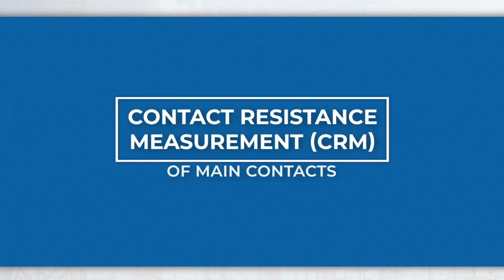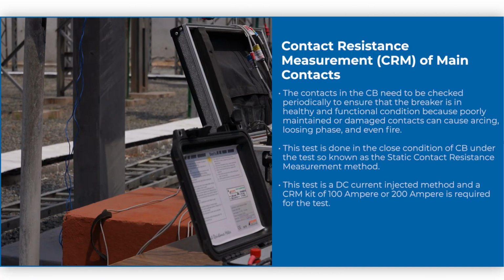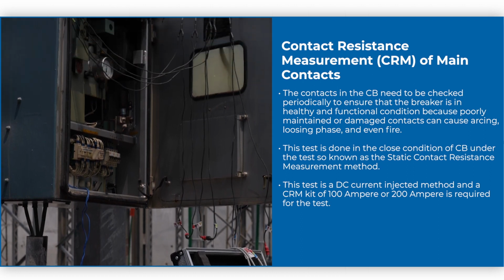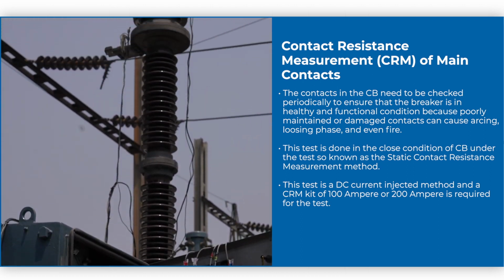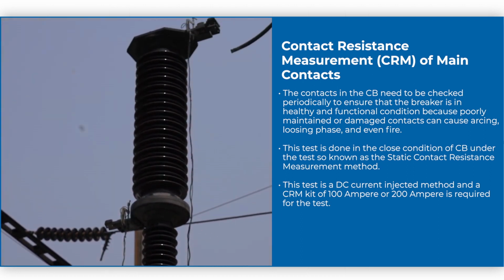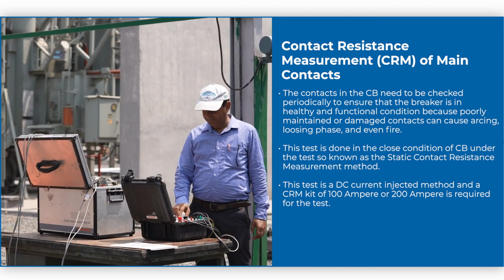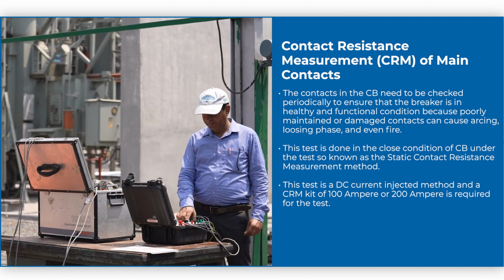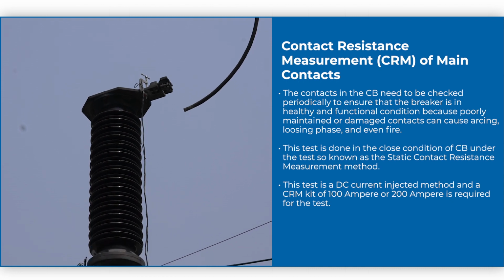Contact resistance measurement (CRM) of main contacts. The contacts in the CB need to be checked periodically to ensure that the breaker is in healthy and functional condition, because poorly maintained or damaged contacts can cause arcing, loss of phase, and even fire.